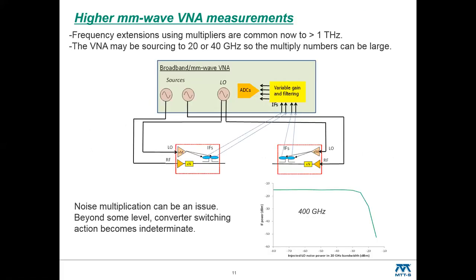So how do these get implemented in practice? One may already be using structures where millimeter wave modules are attached to some microwave VNA. It's a common approach for practical logistical reasons, but it also valuably gets the test port out very close to the DUT, to the wafer probe, or the final structure, so you don't have a crazy amount of loss between the instrument port and the device, which impacts dynamic range, stability, and other things.